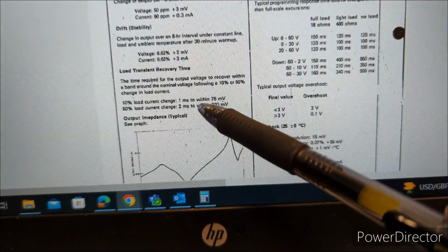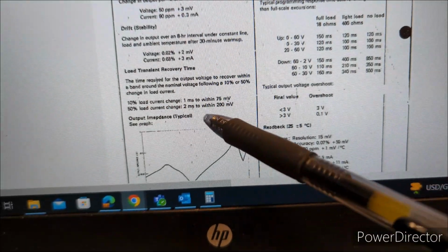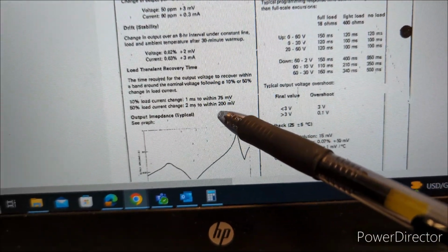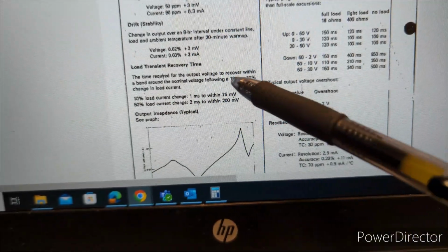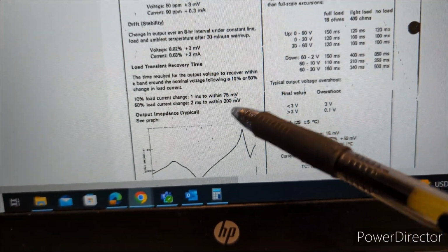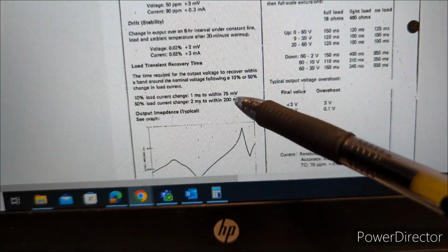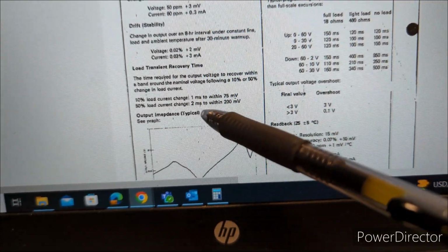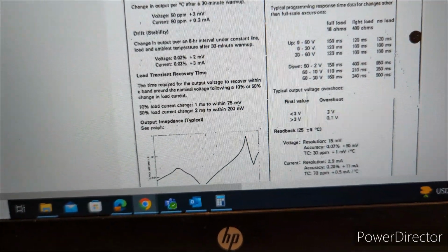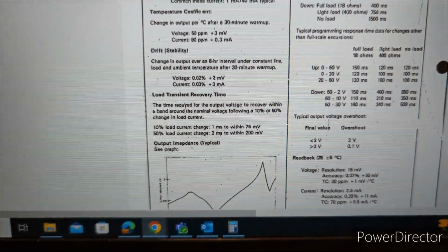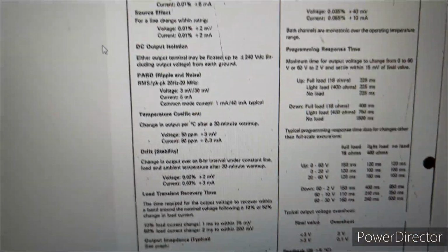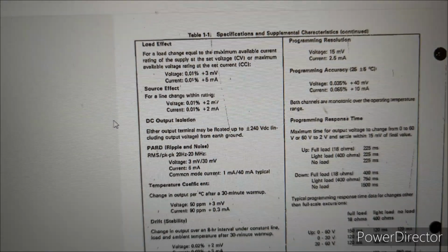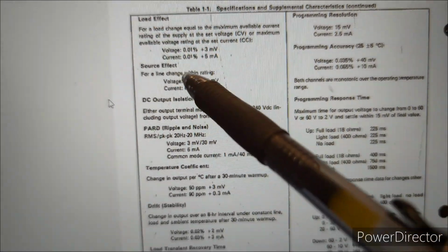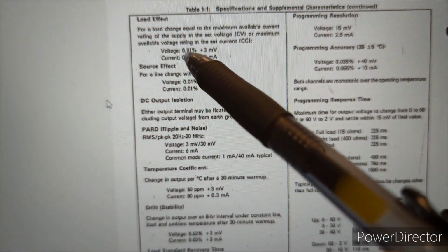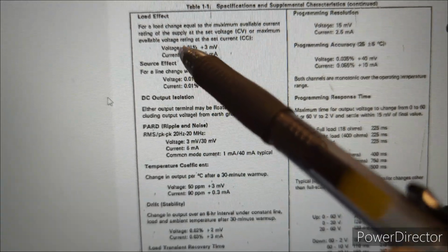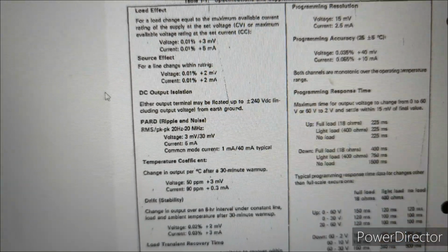Now we did 100% change in load current. So I would imagine that these would be even greater for 100% change. So I think this is a good indication that the supply is operating well within the specs. And so next thing we can look at is load effect, which is, spec is here, voltage 0.01%. So we're looking at, let's do 60 volts, that'll be pretty much 6 millivolts.